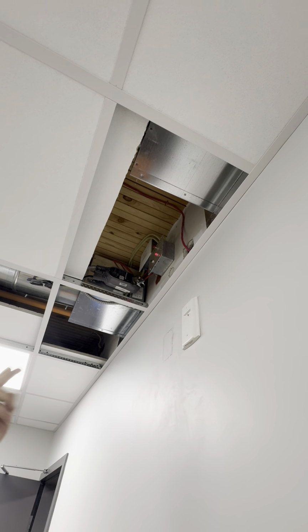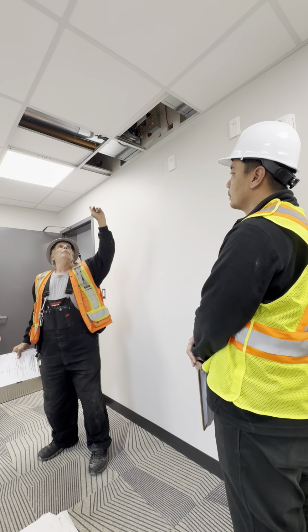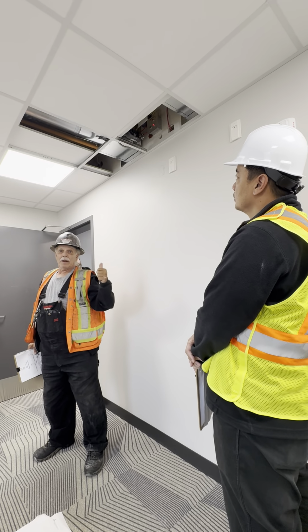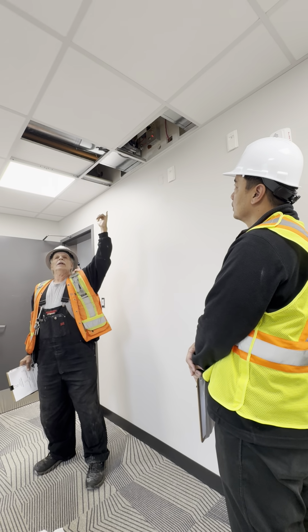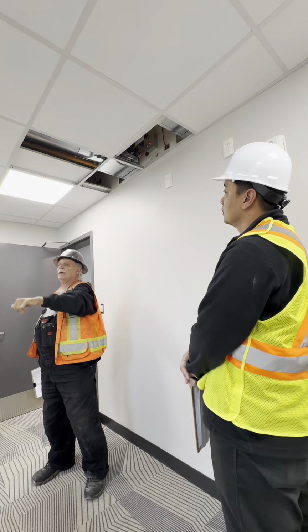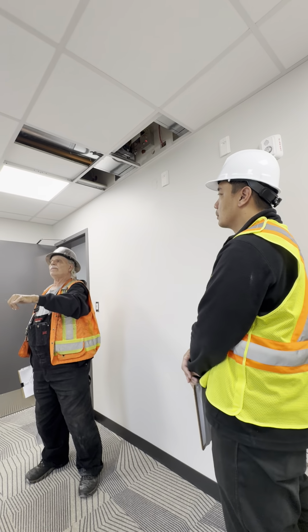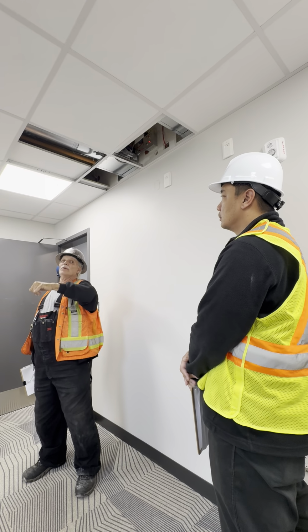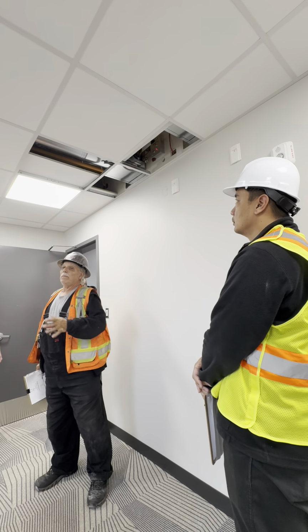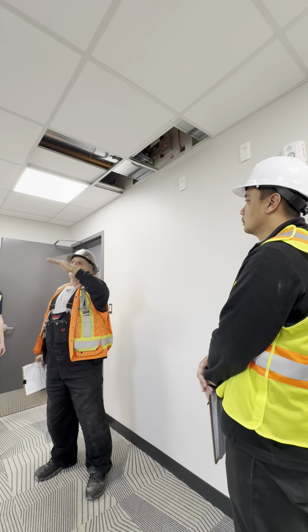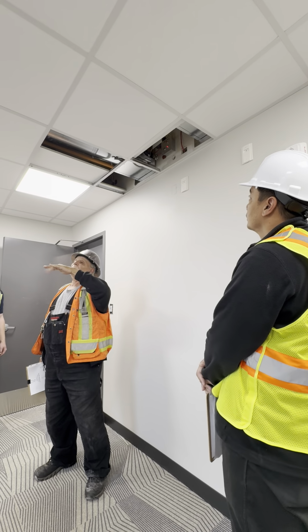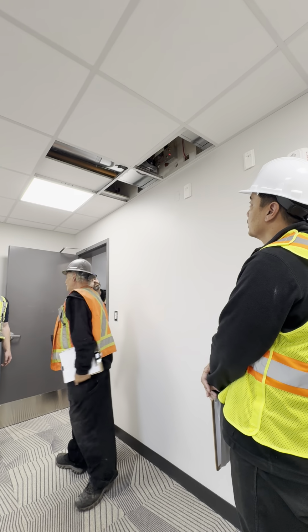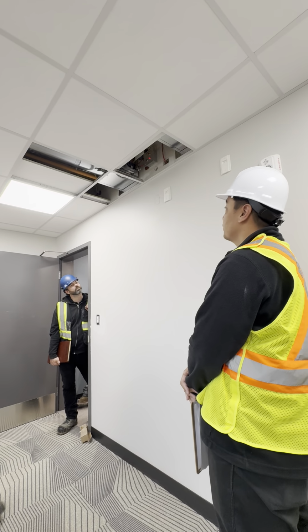So on this damper here, you've got this button, that button, that button. Okay. You've got 3 buttons here. You reset that one. If the smoke was set off in this room, or the fire was in this room, then both those dampers have to be reset with a button. Because the buttons on the side of the dampers are not tied into the fire alarm system. They put an override in so if the alarm goes off, it's going to automatically shut down every single one. But if the sensors in this room haven't gone off, they'll open up automatically. If they don't open up automatically, it's because these buttons have to be reset. So each annual life and fire safety inspection, we have to reset those dampers.